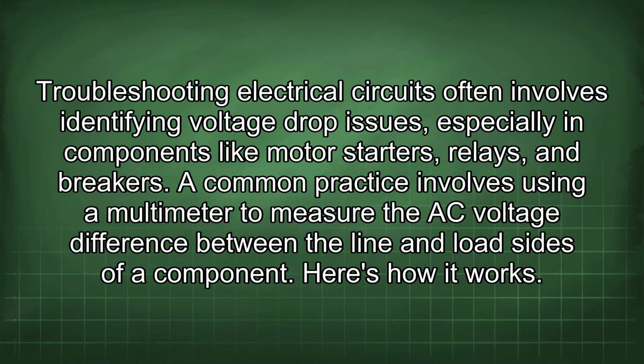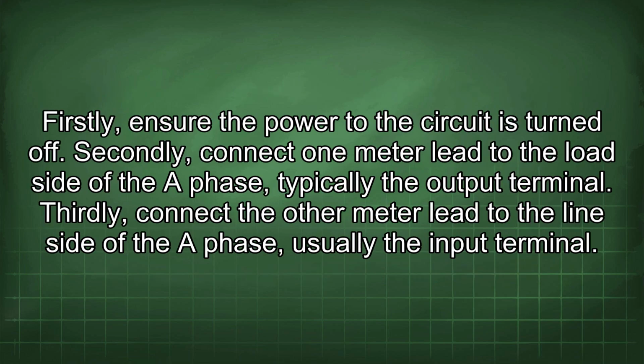Troubleshooting electrical circuits often involves identifying voltage drop issues, especially in components like motor starters, relays, and breakers. A common practice involves using a multimeter to measure the AC voltage difference between the line and load sides of a component. Here's how it works. Firstly, ensure the power to the circuit is turned off.